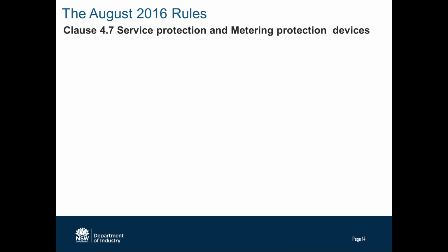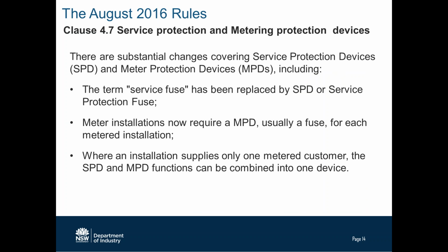the main impact of the changes is this concept of service protection and metering protection devices. There are substantial changes to the rules covering these provisions. We're going away from the term service fuse, and that will now be called a service protection device or service protection fuse. We now will need an MPD or meter protection device, usually a fuse, for each metered installation. The reason for this is that the smart meters are only rated at 80 amps. They have a contactor in them that's rated at 80 amps, so a 100 amp fuse will not protect those meters.